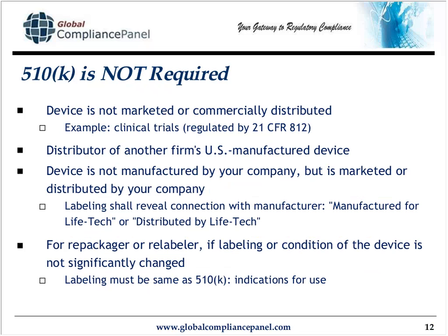There are situations in which a 510K is not required. A device isn't marketed or commercially distributed. Perhaps you're doing clinical trials. The devices are never leaving your control, or a CRO, clinical research organization, that's operating as your firm, so to speak. If you distribute another firm's U.S. manufactured device, you're just a distributor.